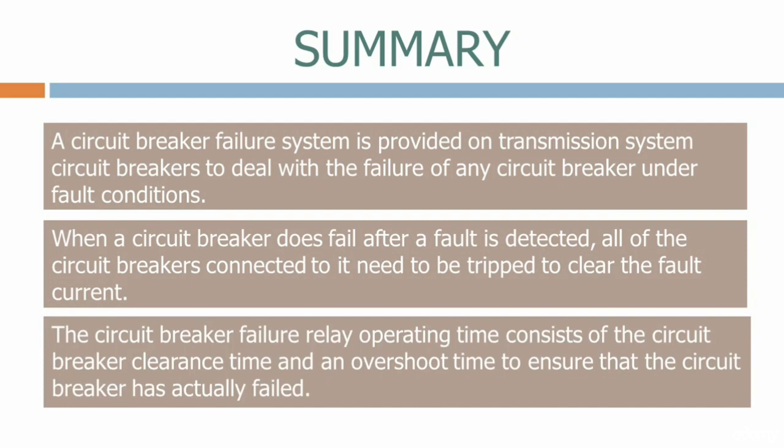The circuit breaker failure relay operating time consists of the circuit breaker clearance time and an overshoot time to ensure that the circuit breaker has actually failed.